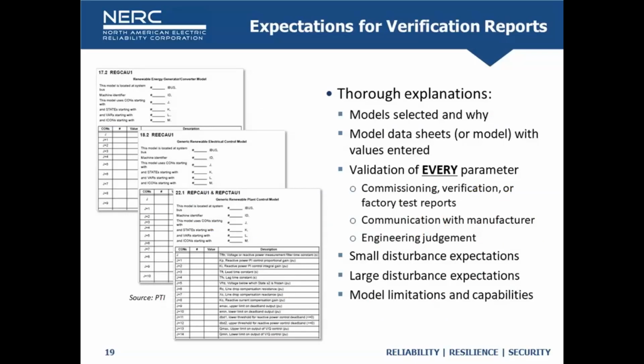Because verification can be comparison with a spec sheet, or maybe this is a measurement time constant, and so there's an expectation that that's going to be 0.02 because it is in every other model out there in the world, right? So we can check off a lot of these to say, well, it's a default value. This is in there to make the model work. It's not related to a controller setting. And so there goes about 15-20% of the parameter values.